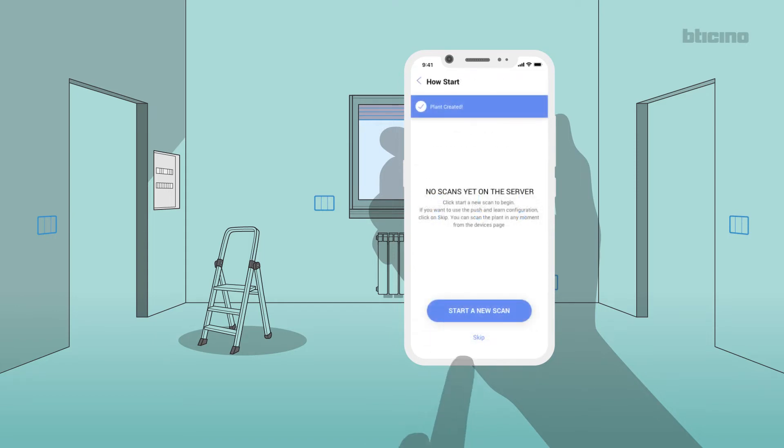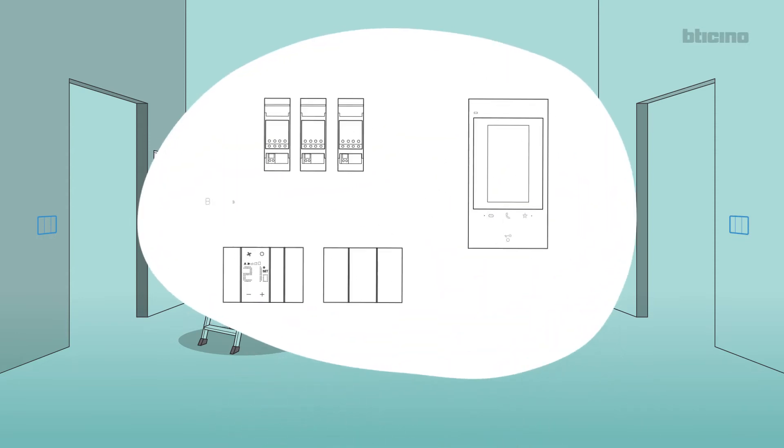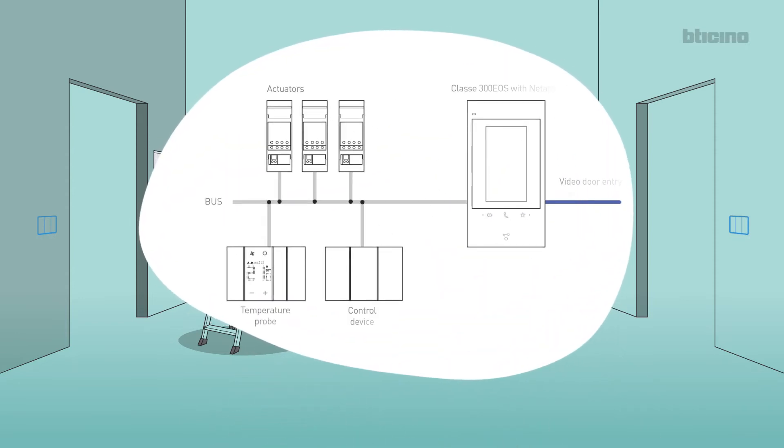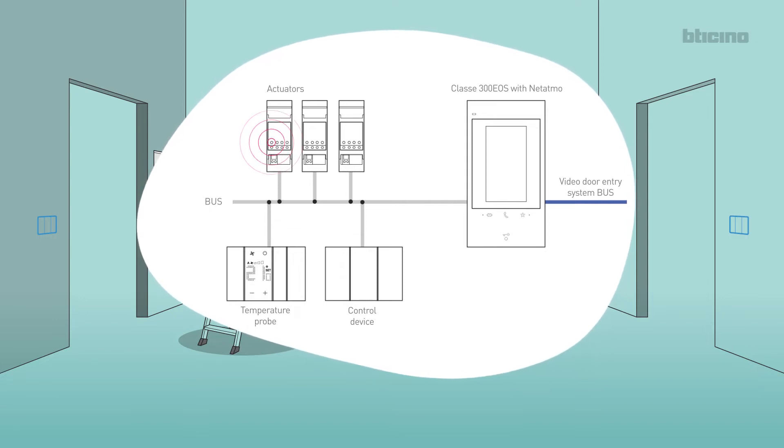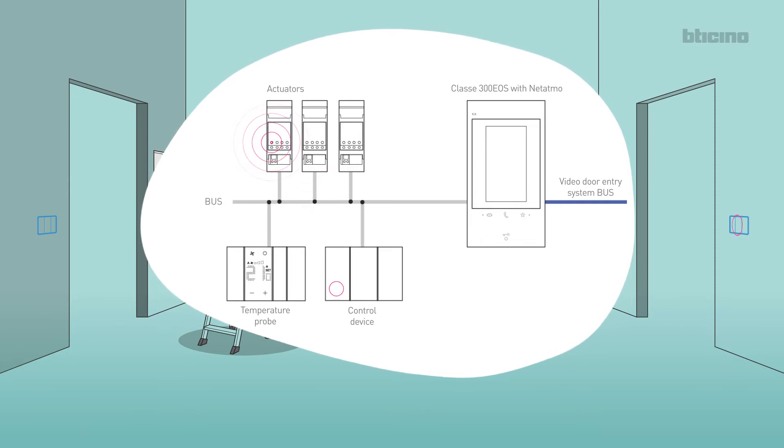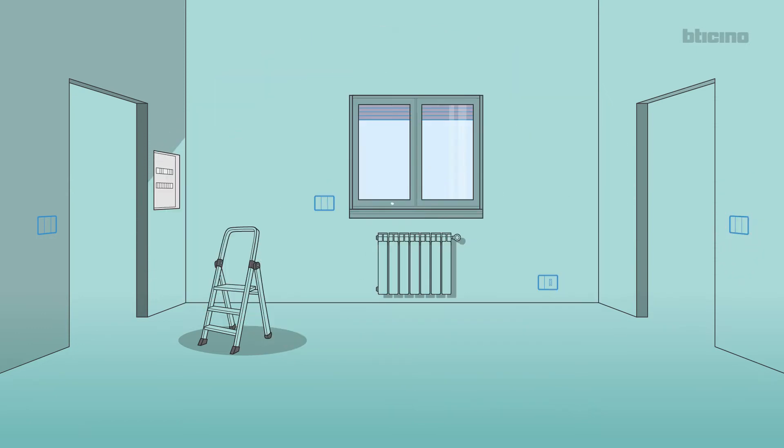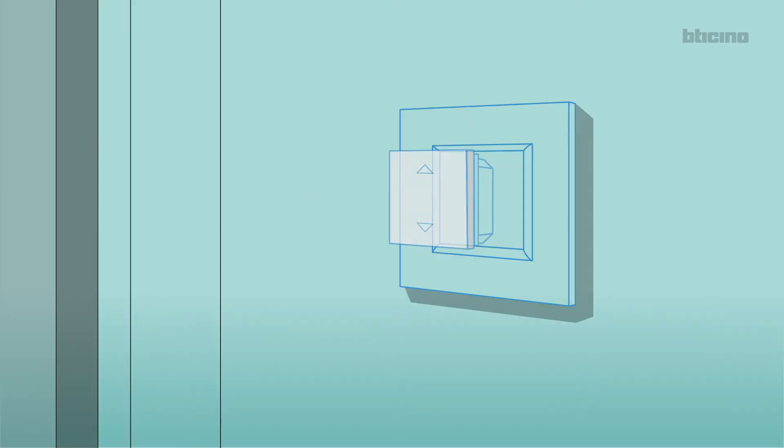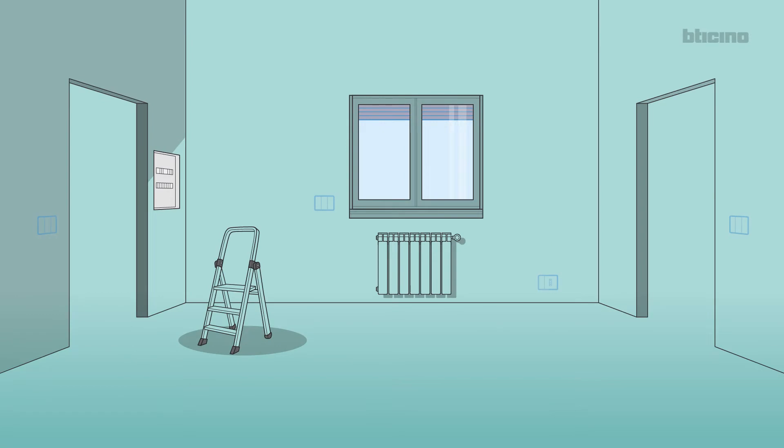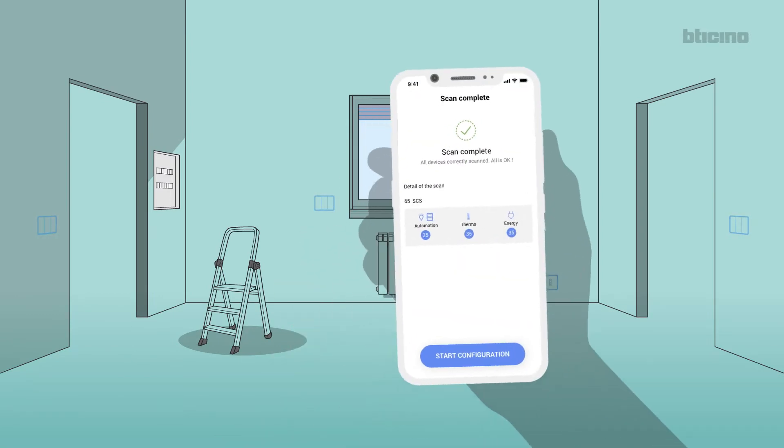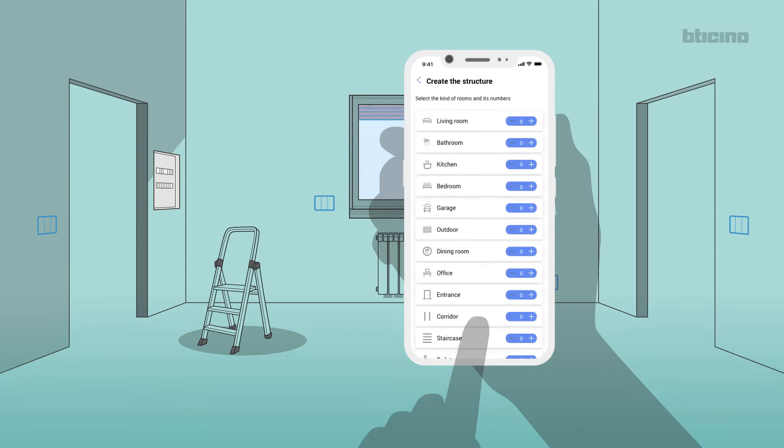If you select Skip, you can use the Push & Learn procedure for manual recognition of devices. Select the actuator by pressing one of its keys and press on the control device to be associated. This procedure is useful for easily adding a new device to the system or to configure a system with a few devices. Continue by selecting Start Configuration.